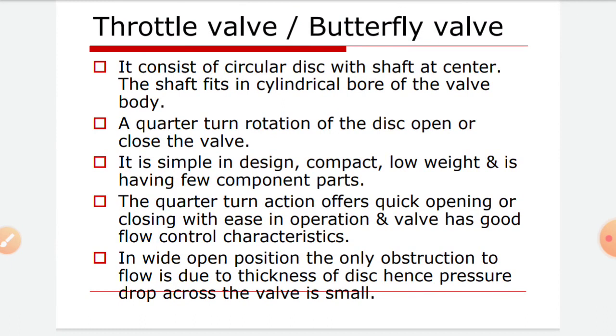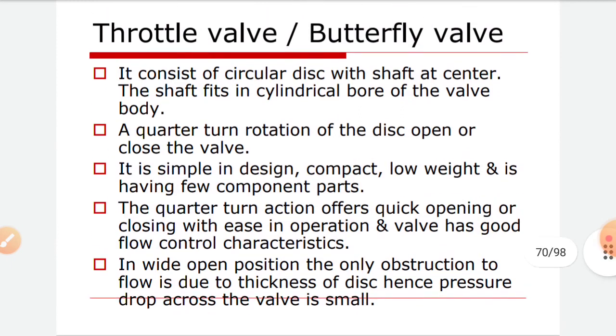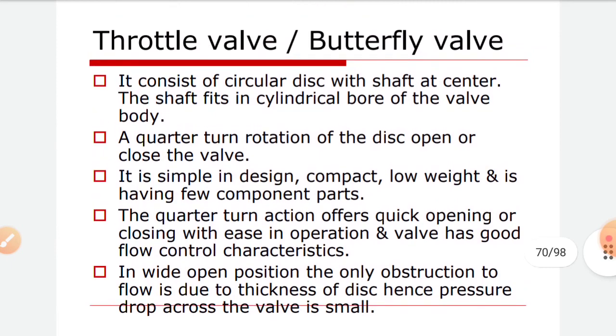It is simple in design, compact, low weight, and has few component parts. The quarter turn action offers quick opening or closing with ease in operation, and the valve has a good flow control characteristic. In the wide open position, the only obstruction to flow is due to the thickness of the disc, hence the pressure drop across the valve is small.